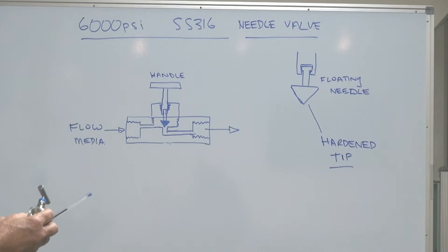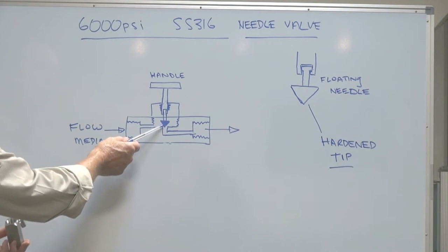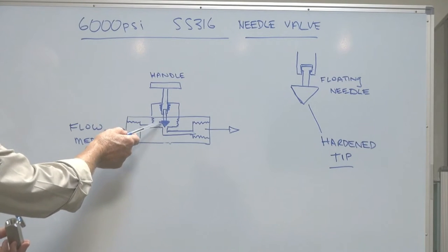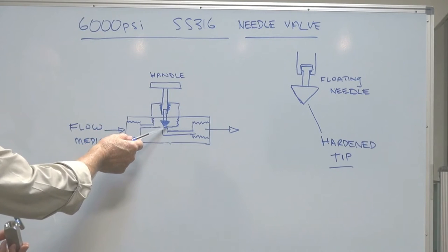They're not a full flow valve. They actually have a small orifice inside with a hardened tip - a floating tip. There's a handle, and you screw this up and down, and the needle will go into the orifice.